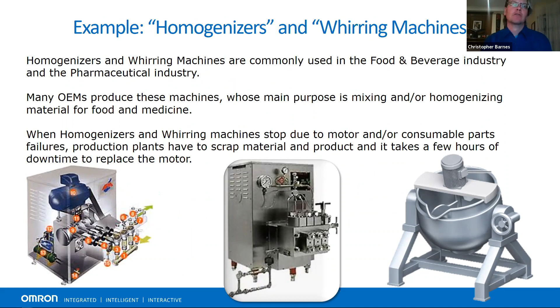This is where it gets interesting in terms of the data, being able to pick this up and what it looked like using current analysis sensors. So this is basically getting the electrical feedback off the electric motor. You're able to pick up a problem with a gasket on the equipment.